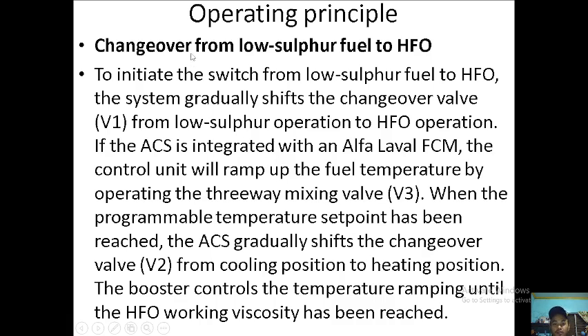If you want to change over from low sulfur fuel to heavy fuel oil, the low sulfur fuel has a temperature of around 30 degrees, while the HFO has a temperature of more than 120 degrees. So it goes from cold fuel to hot fuel. To initiate the switch from low sulfur fuel to HFO, the system gradually shifts the changeover valve from low sulfur operation to HFO operation.